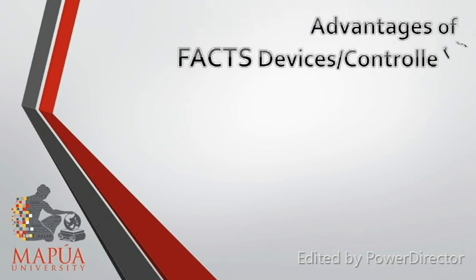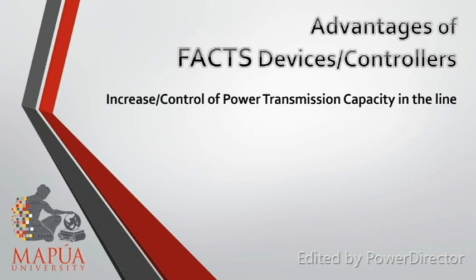Here are the notable advantages of FACTS devices and controllers. As FACTS can alter the impedance in the line, it increases and controls power transmission capacity in the line as ordered. The use of control of power flow may be to follow a contract, meet the utility's own needs, ensure optimum power flow, ride through emergency conditions, or a combination thereof, and prevents loop flow. And in the same way, it increases the loading capability of the lines to their thermal capabilities, including short-term and seasonal limits.